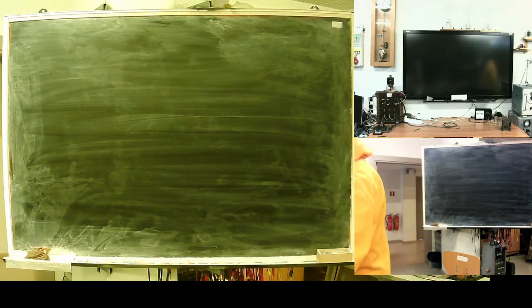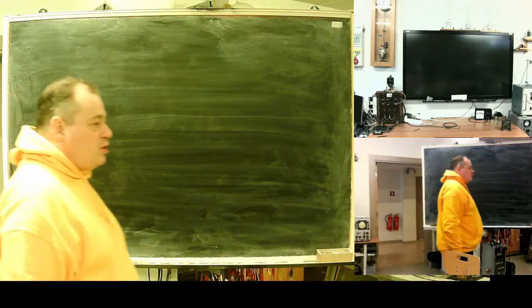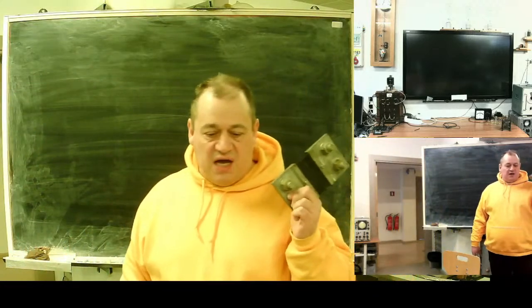It's a bigger brother of, for example, this one. 0.1 ohm precise resistance, rated for 5 amps. Yeah. Put 5 amps here, and you will get 5 multiplied by 0.1 volts here. Put 1.5 thousand amps here. This one is for 1.5 kiloamps. And you will get 75 millivolts here. It's a measuring resistance. Good thing, you can scale down your current. And sometimes they are used.